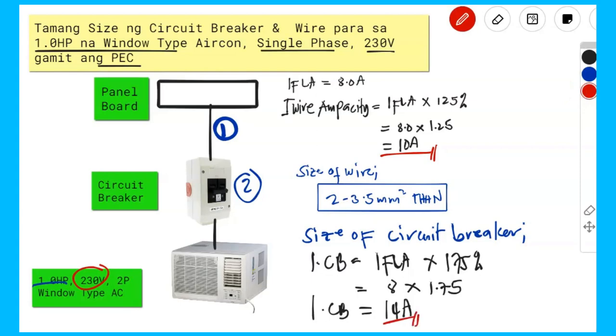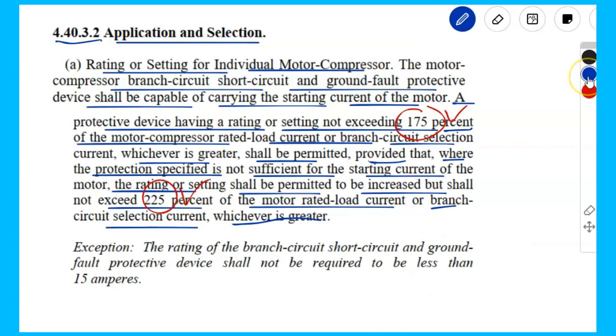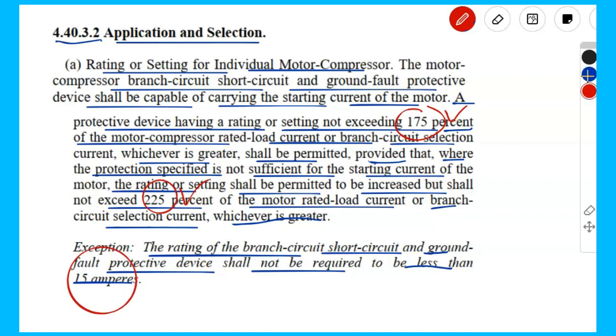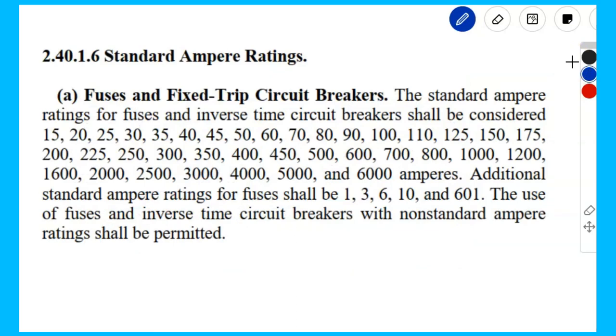And then may sinabi sa code, basahin natin ulit, that the rating of the branch circuit, the short circuit and the ground fault protective device shall not be required to be less than 15 amperes. So sa resolve natin kanina, nakakuha tayo ng 14 amperes. So from this, hindi raw siya dapat less than ng 15 amperes. So, ano ba yung next na size ng circuit breaker sa 15 amperes? Tingnan natin uli yung Philippine Electrical Code. Ang sabi sa 2.40.1.6, the standard ampere ratings, the fuses and fixed-trip circuit breakers.